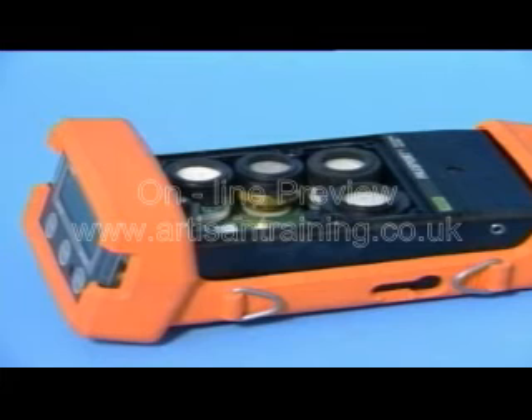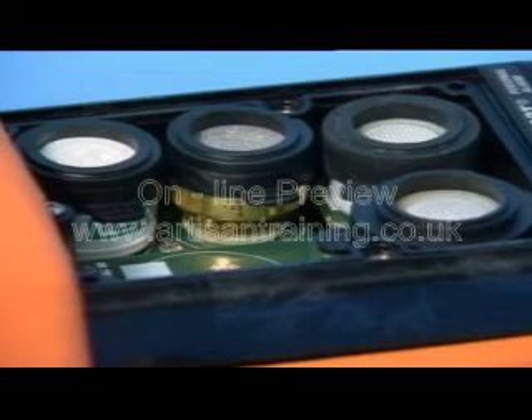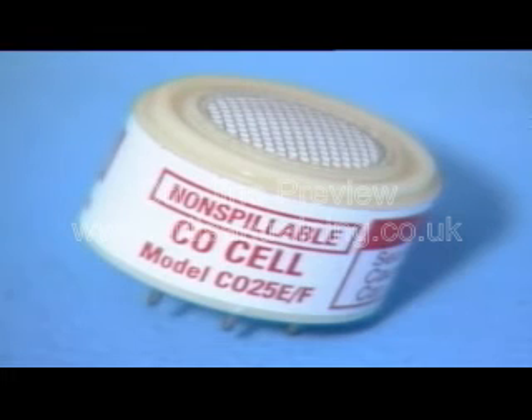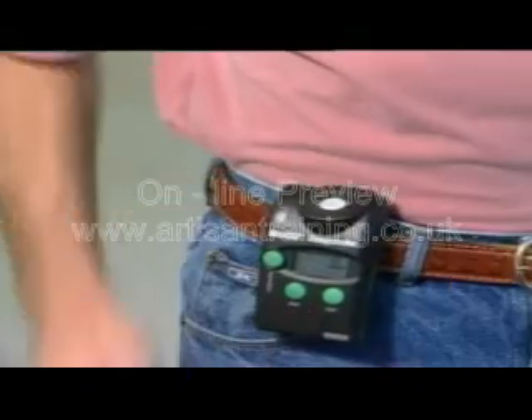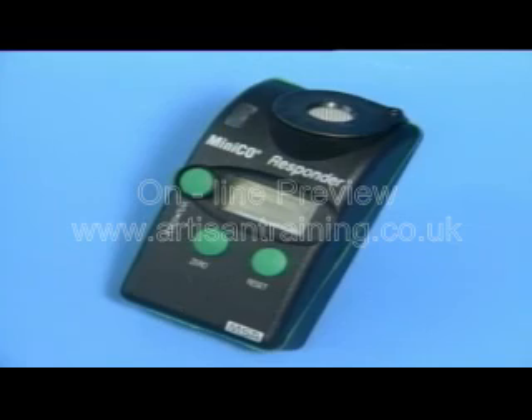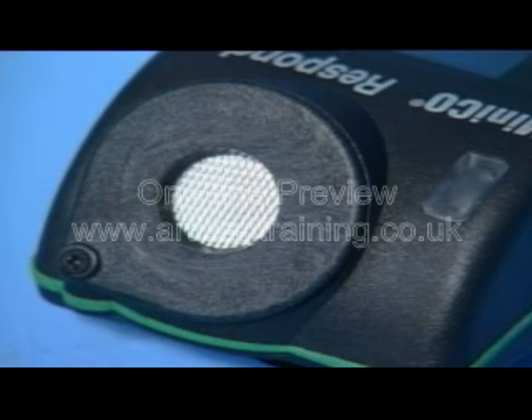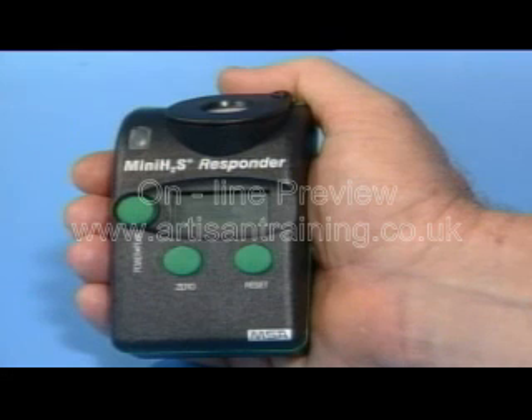Some instruments, known as multiple gas monitors, are able to detect two or more different conditions or substances, owing to the fact that they incorporate several sensors. Each sensor is manufactured to react to a specific substance or gas type. Another type of instrument is this single gas type, designed purely to detect one known or likely gas. Single gas monitors use only one sensor, designed to detect one type of substance or target gas.